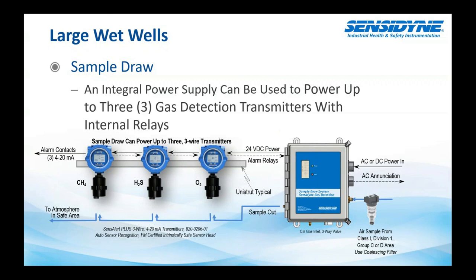Okay. And then a question about calibration. How often do you need to calibrate the sensors? So that's a very subjective question. We recommend no more than quarterly. But it is dependent upon your maintenance setups, and it really depends upon the environment the sensor's in. If you've got it in a wet well, you should be calibrating that more frequently.